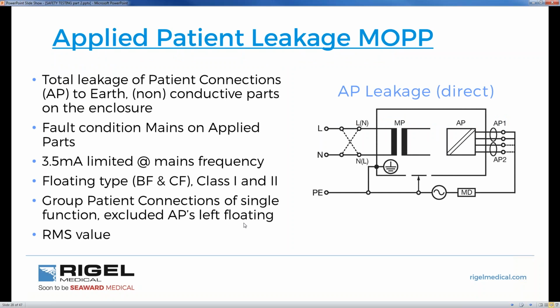Applied part leakage, means of patient protection. Total leakage of patient connections, AP to earth, non-conductive parts of the enclosure or chassis. Very similar to mains on applied part. It is the direct comparison to 60601 mains on applied part. So we put mains out from an isolated voltage within the Rigel onto the applied parts. Again, it's current limited, but the current limit is slightly less than 60601. And we're measuring the RMS value.